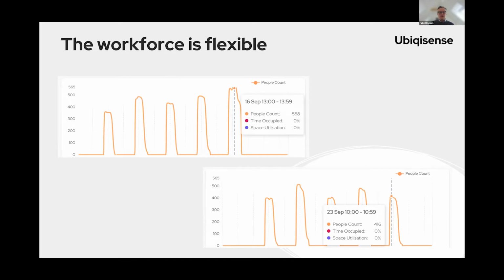One of the things this customer immediately realized was that people show up for work later than anticipated, and they also leave the office quite a bit earlier than anticipated when programming the building management system. So one immediate saving they made, based on our numbers from the people counting sensors, was to start the ventilation half an hour later and stop it half an hour earlier in the day. That immediately saved them around 30,000 kilowatt hours per year.